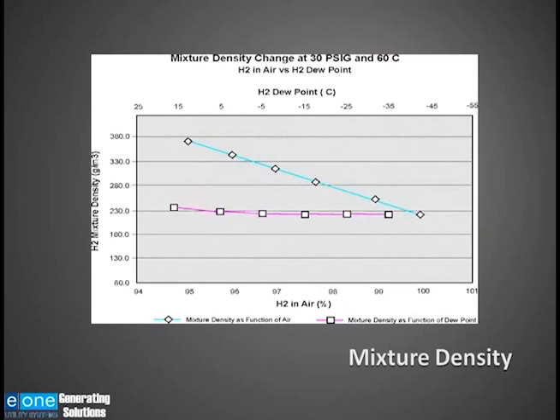This is a chart I mentioned earlier that supports the fact that a change in dew point has little effect on the density, which would mean that it has little effect on the efficiency of the generator. You can see from this slide, and by the way, this slide was created by NASA, that going from plus 15 degrees C to minus 15 degrees C has very little effect on the gas density, meaning a 30-degree swing in dew point will have little effect on the generator efficiency. However, you can see that purity has a major effect on the density.